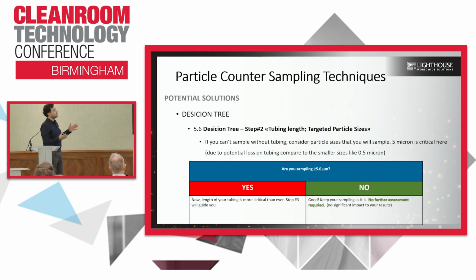We take you to the tube length. When you come to this point, are you sampling 5 microns? Because the tube length discussion generally comes from the 5 micron particle losses in tubing. With 0.5 micron, you are slightly on the safer side of the process, but 5 micron is critical. If you say yes, then in step number 3 we will look at how many bends you need. Or if you say, no, I'm not sampling 5 micron, then no further assessment is required.